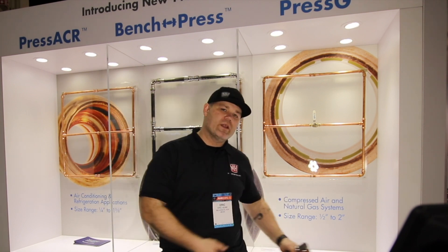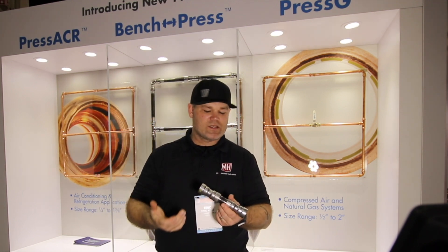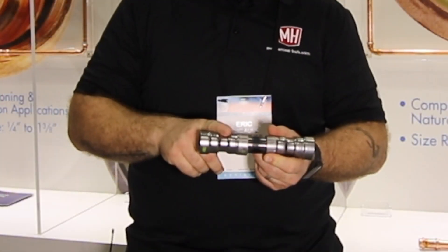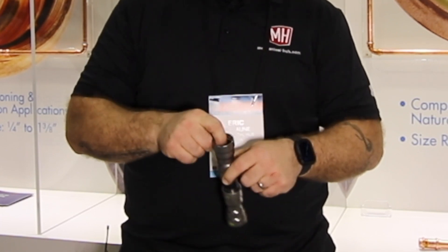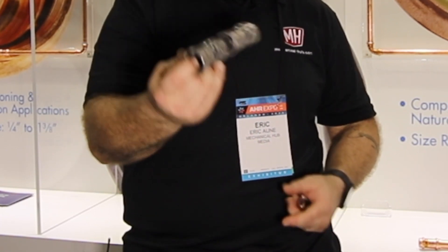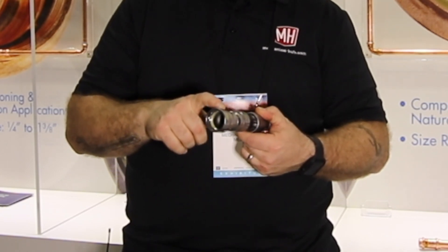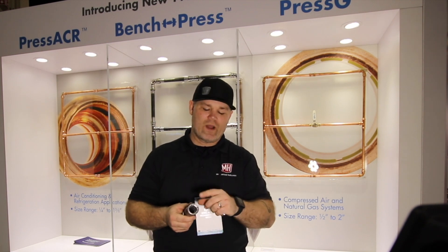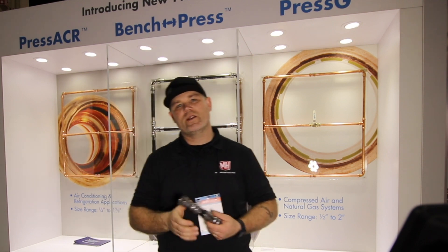Totally new from NIBCO is the Bench Press. This is a carbon steel iron pipe press fitting system. One variety uses water sealing elements; the other uses the HNBR sealing element for gas — so you choose one or the other. They're coming out with this from half-inch up to two-inch this summer.